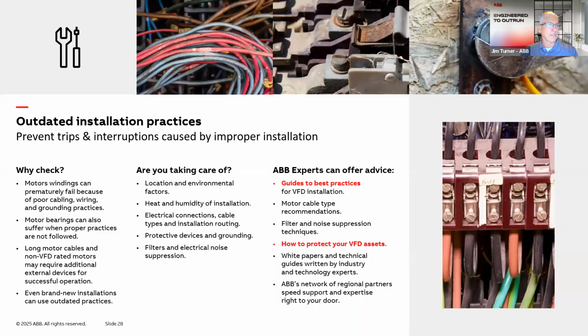So, motors and couplings need to be aligned and lubricated to avoid unnecessary wear. VFDs and other motor controls need to be grounded properly. Maybe specific types of motor cables need to be used so you'll be free from nuisance trips. What we do is publish a best practices guide on how to install VFDs correctly: proper cabling, electrical practices, grounding, bonding, things like that, to meet code and offer a long operational life.